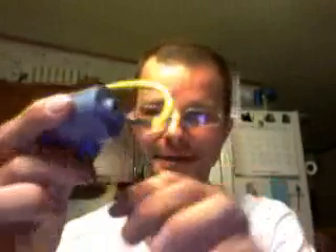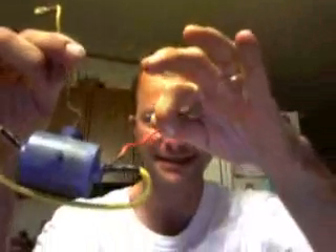I went to the truck and got a three-wire hard start — a potential relay and capacitor combination that I find works very well. I installed that, put the amp probe on it, pushed the contactor in, and this time it pulled 45 amps on startup and settled down. I thought, well, it's likely not my hard start kit. I looked up and noticed the little soft start device was still in there — a device I have a very low opinion of.